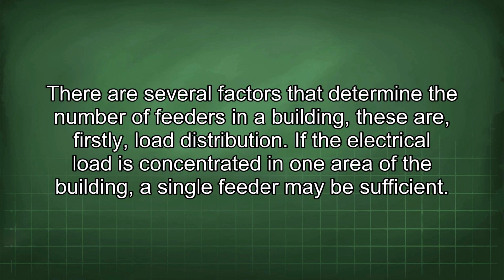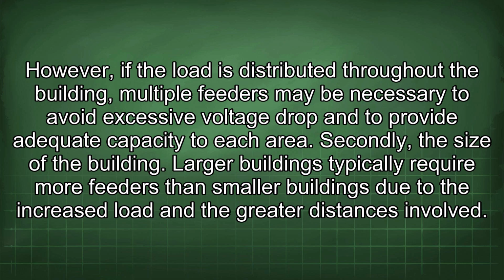There are several factors that determine the number of feeders in a building. These are, firstly, load distribution. If the electrical load is concentrated in one area of the building, a single feeder may be sufficient. However, if the load is distributed throughout the building, multiple feeders may be necessary to avoid excessive voltage drop and to provide adequate capacity to each area. Secondly, the size of the building. Larger buildings typically require more feeders than smaller buildings due to the increased load and the greater distances involved.